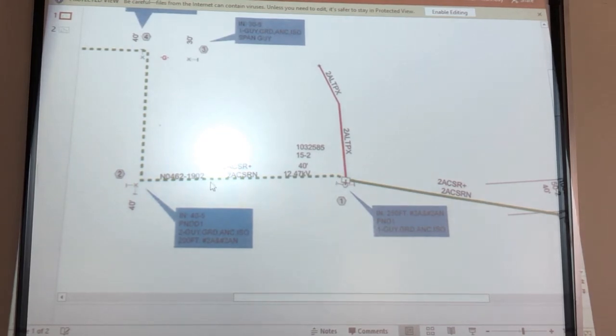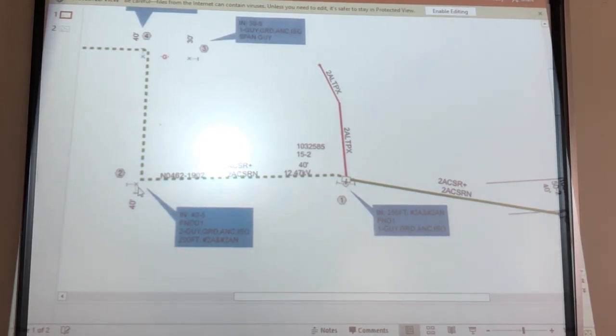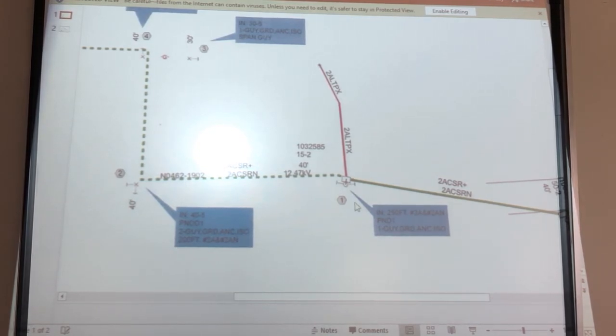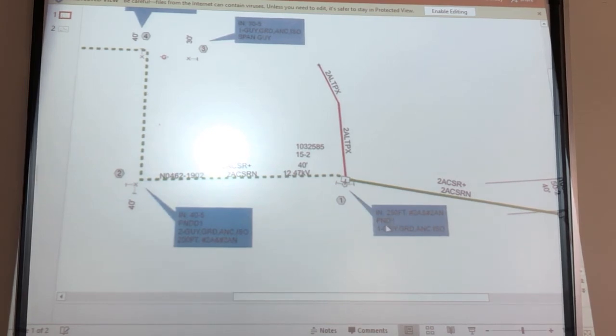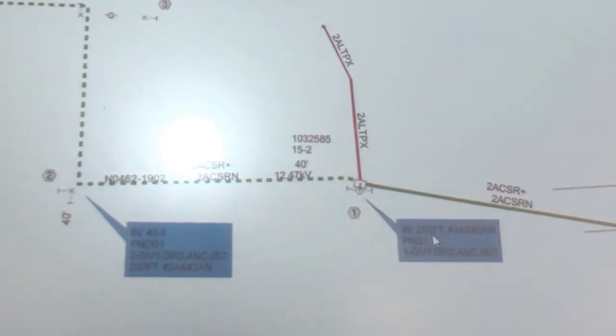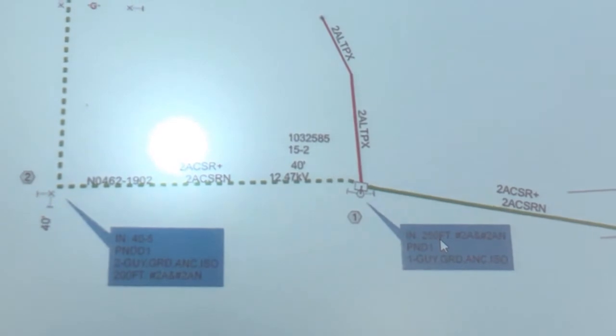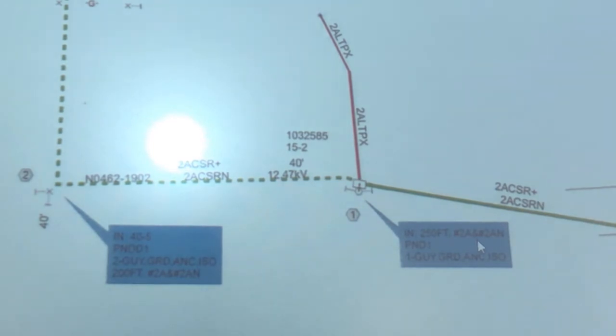This wire, span the wire here, which is 250 feet, is indicated right here. You're just in 250 feet, number 2 aluminum. That's for your neutral and your primary conductor, times 2.